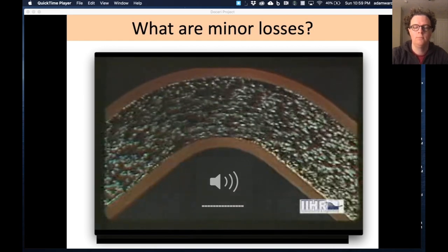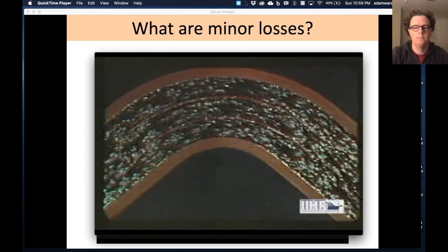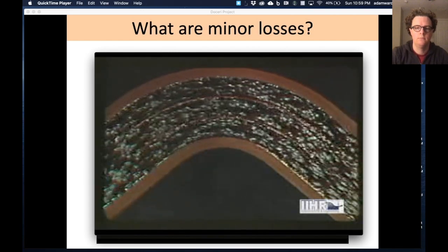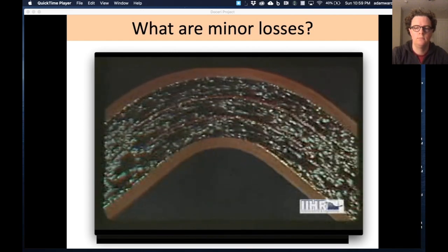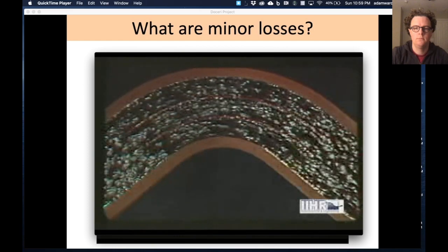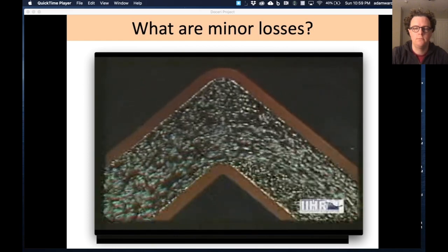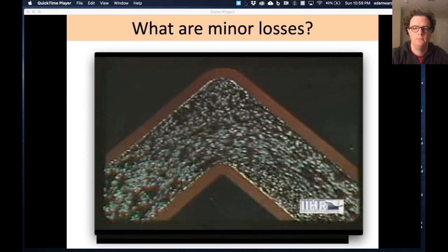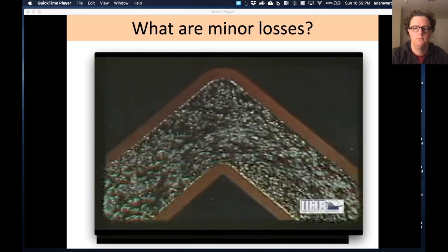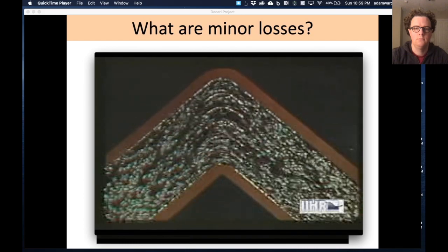A change in the pressure field as a whole is provided by the introduction of guide vanes. These can be made to conform to the original boundary and thus increase the relative radius of curvature locally, or else the whole structure can be redesigned accordingly, as in the case of this miter bend. The flow is obviously much worse without the vanes, but much more efficient once vanes have been installed.